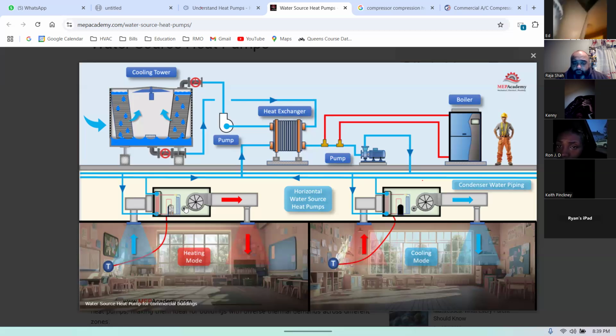So now my coil is super hot. So when the air comes in, it's going to go across a hot coil and heat up the space. So it's getting the heat now from my boiler - we're injecting heat into the line. Really, in this situation, you can kind of just turn off the cooling tower altogether. You no longer really need it if we have the boiler putting out the right amount of heat.